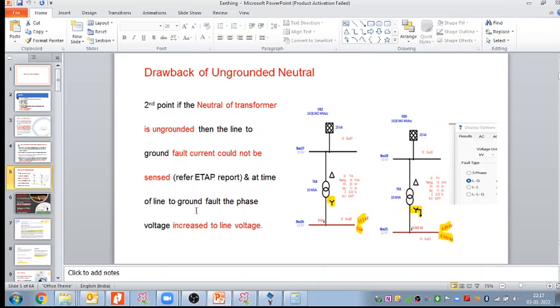And at the time of a line to ground fault, the phase voltage increases to the line voltage. Here is a delta star earth example. If we take a delta star ungrounded system, then the phase voltage jumps to the line voltage, and the fault current is 0. If I just earth this neutral, then what will happen? We can sense the fault current, that is 6.543 kilo ampere, and the phase voltage remains the phase voltage, it is not jumping. So this is why we provide the earthing or grounding for the neutral.